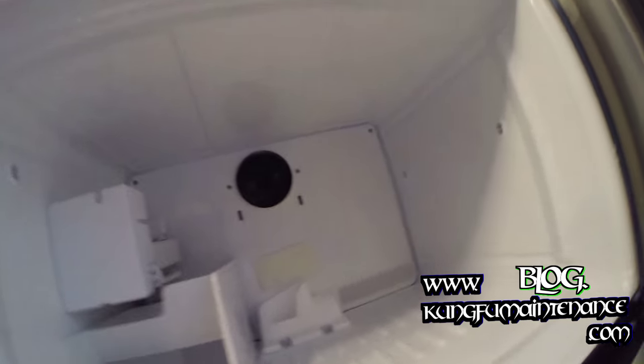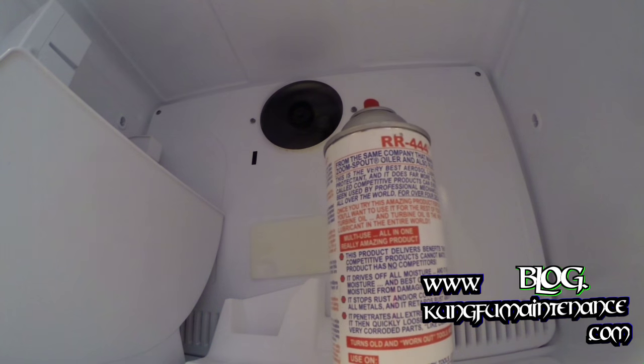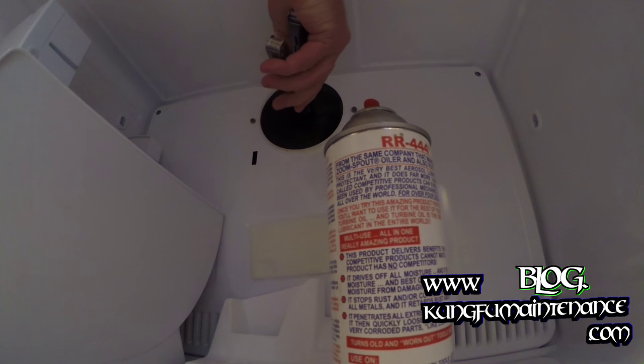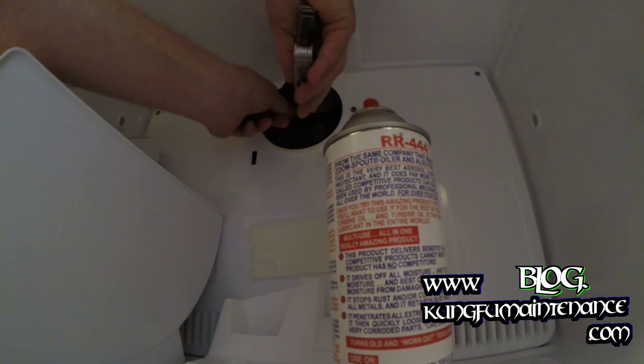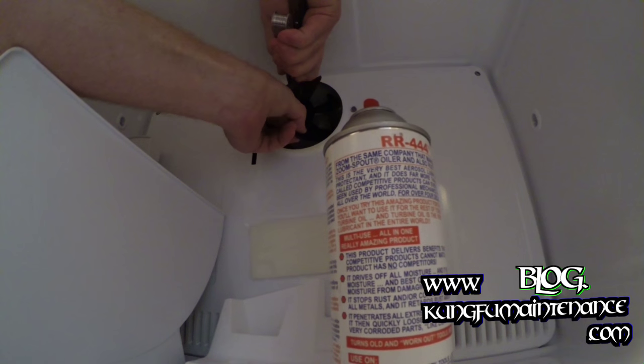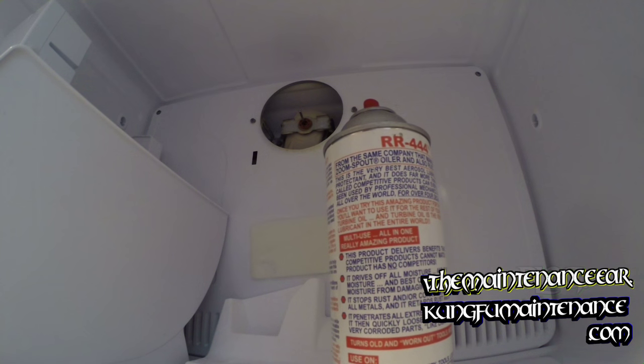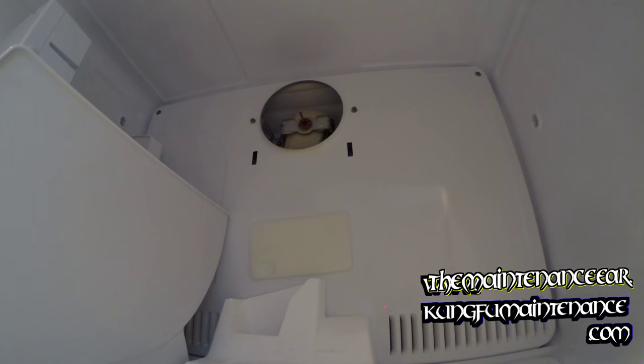And pull it back off after. Okay, so went and got my trusty RR-444. This may or may not work on this one. It is what it is. Pull it off. Definitely it's our motor, so it's not too expensive to replace the fan motor. Not a big deal if that's needed, but let's try the lube here and see what happens.